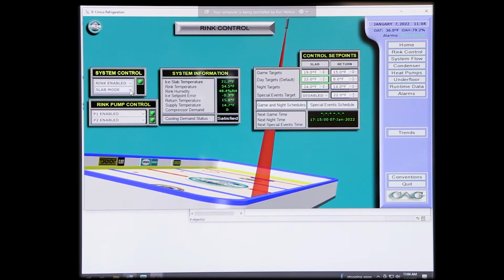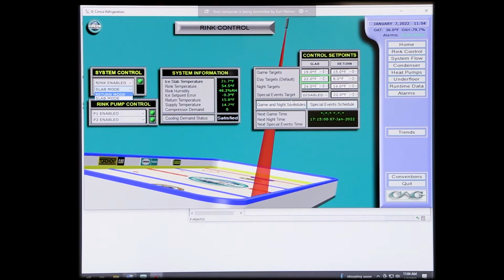You have two options to run on this system. You have slab mode and you have return mode. In return mode, the pump runs all the time and we target a specific temperature, the lowest of which is 8 degrees, as you can see here in return. You can run return in a game target, in a day target, and a night target. Anything that's not programmed into the schedule down here in game and night schedules will revert to day target. Day is default.